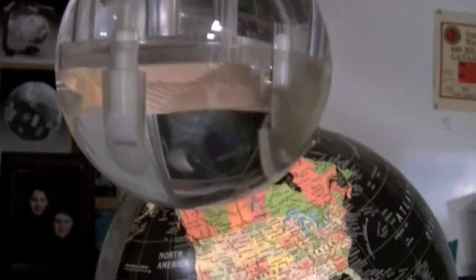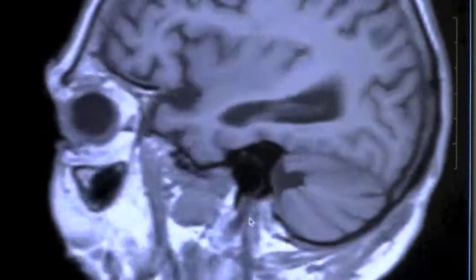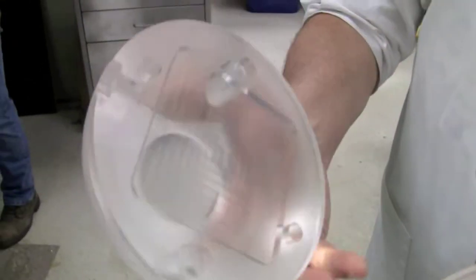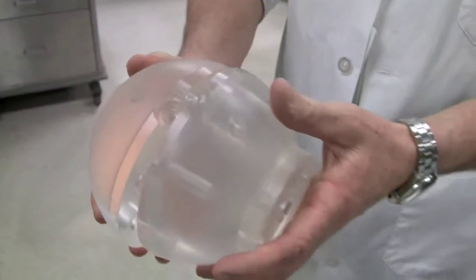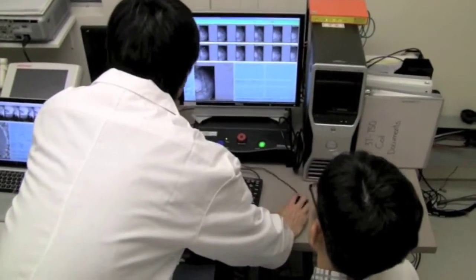Like this Lucy Phantom — while it may look like a plastic ball, it's actually helping patients around the world with inoperable brain tumors. With the same weight and density as the human brain, Lucy checks that each radiation beam in the treatment plan will actually hit the patient's tumor within sub-millimeter accuracy.